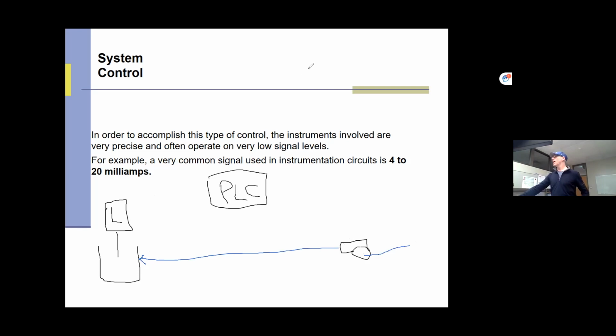Okay, so in this case here, I have some water in this tank. It looks like this tank's pretty empty right now. So if this tank's empty, my level transmitter is going to have a zero reading. It's zero, which means, remember, 4 milliamps, which means there's no water. So the signal coming out of my level transmitter, or my sensor, is going to go to my PLC. And that's my brain, that's my computer. Inside the PLC, there's a program. That program's going to say, hey, when this device here is 0, I need to send a signal to the pump. So there's an input side of a PLC and an output side.